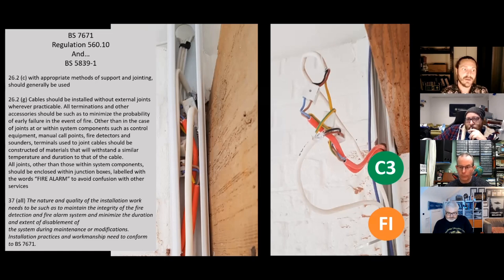And I'm just thinking, if there was a fire here, what's the scenario? Because if somebody was to die due to a fire, bear in mind there's going to be a fire investigation. What was the cause of the death? So they work their way back, and it's like, has this been installed right? If it was documented that this temporary join was made last night, obviously the person who did this would be quizzed and asked, why did you do it like this? And have you taken all reasonable steps to make sure you're getting it up and running? Because, of course, maintenance is required. Things happen.